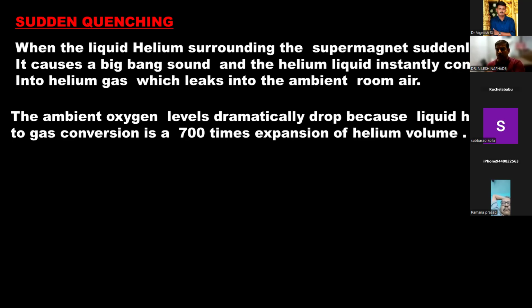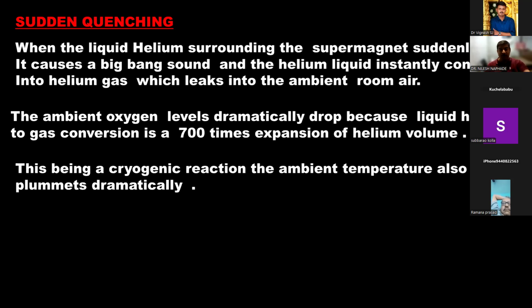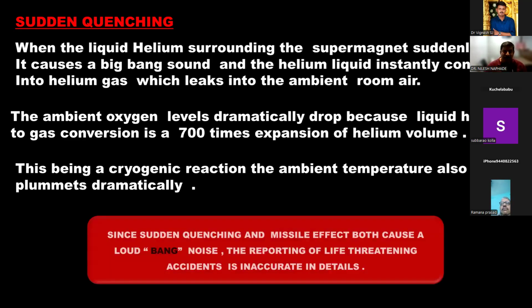At such times, if your child is already on supplemented oxygen, that child will not fall prey to the helium. You will be able to lift up the child and leave the room before the helium takes over. This poor child became hypoxic because she must not have been on oxygen. This liquid helium converting into gaseous helium is a cryogenic reaction, so the ambient temperature also plummets dramatically. Everything becomes cold, because the conversion into gas is a cold-generating reaction.